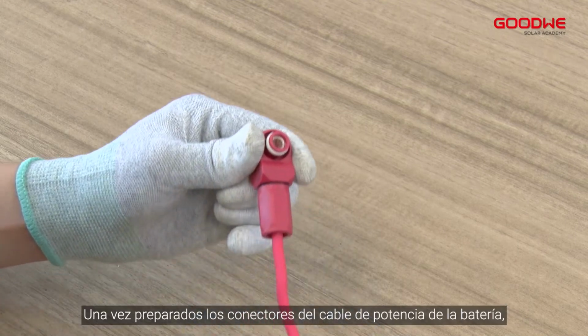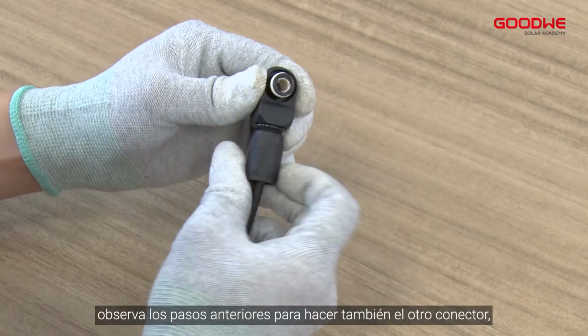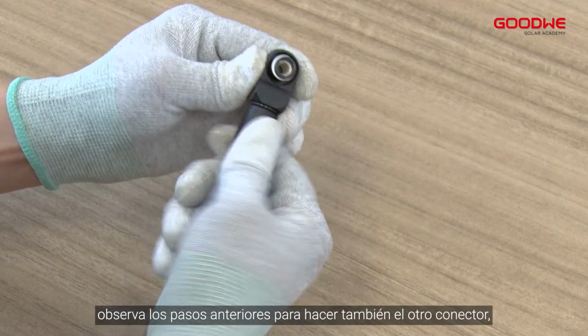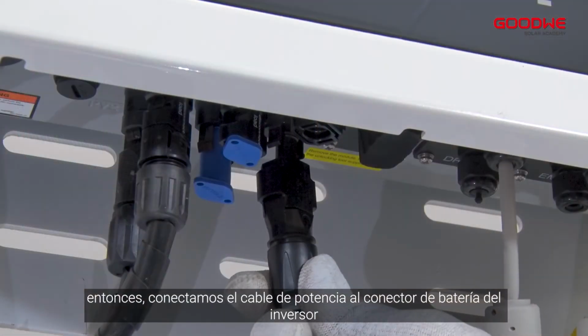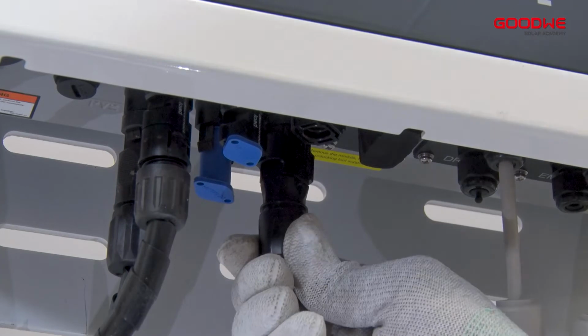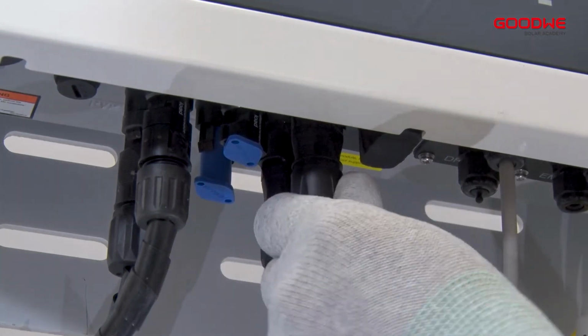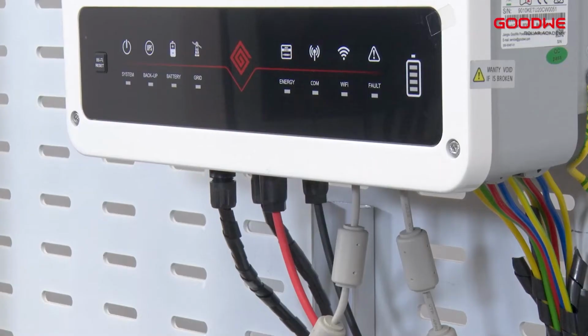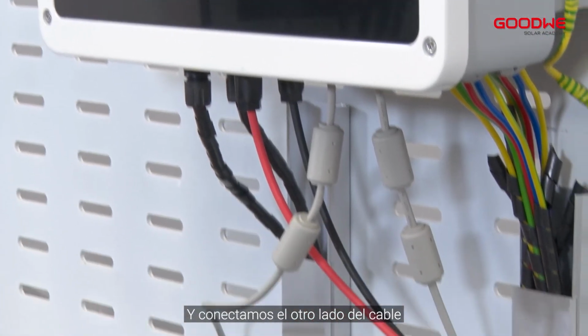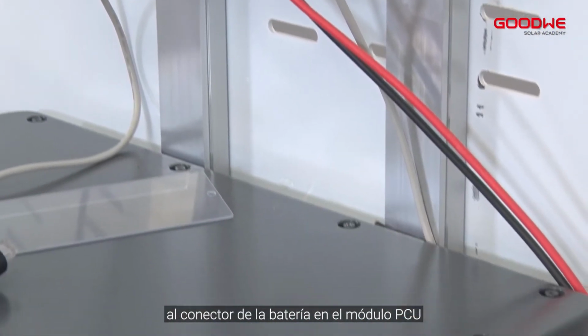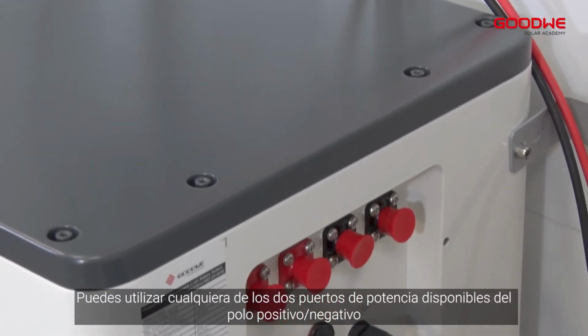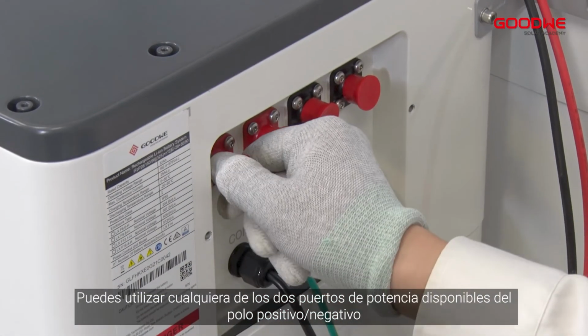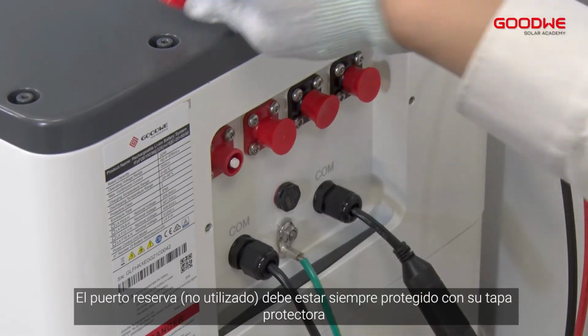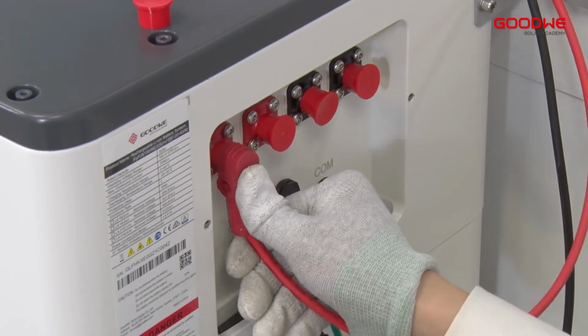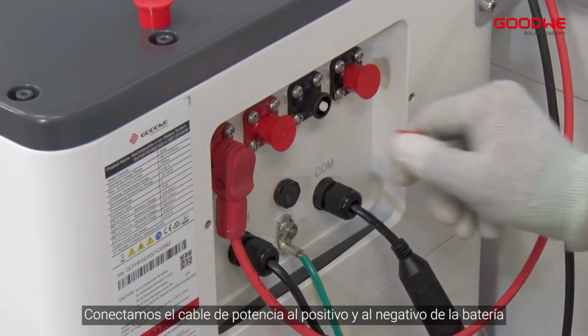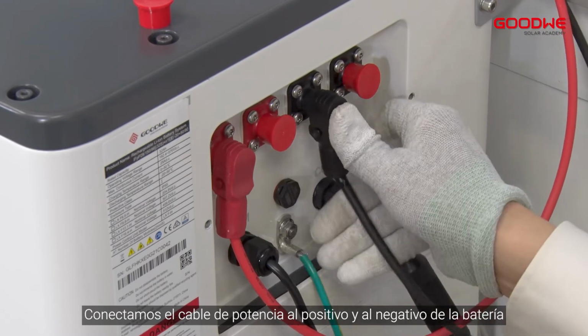When the connectors of the power cable have been made, follow the above steps to make another connector. Then connect the connectors to the battery terminals of the inverter, and plug it in. And then we connect the other side to the battery power connector on the PCU box. You can use any one of the two power ports of positive-negative port. The reserved one should be protected using a cover. Connect the power cable to battery positive and battery negative.